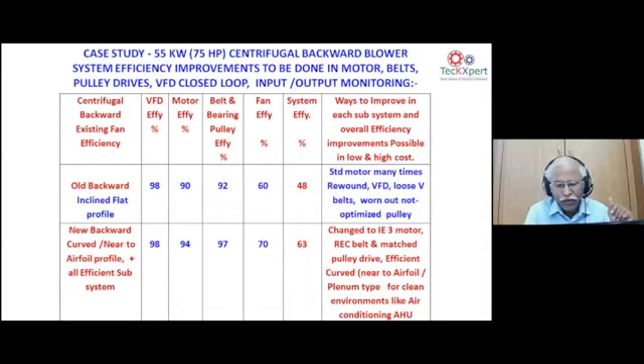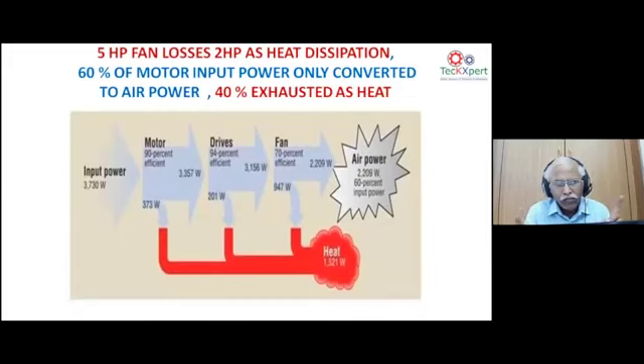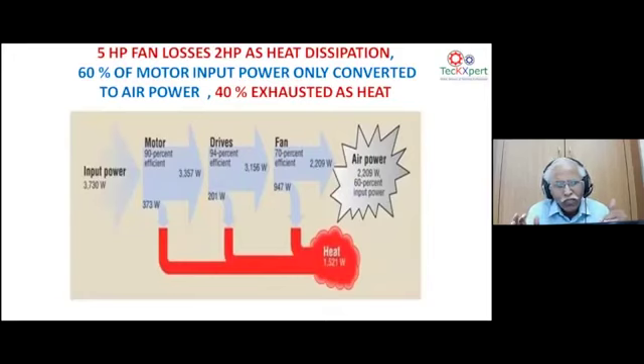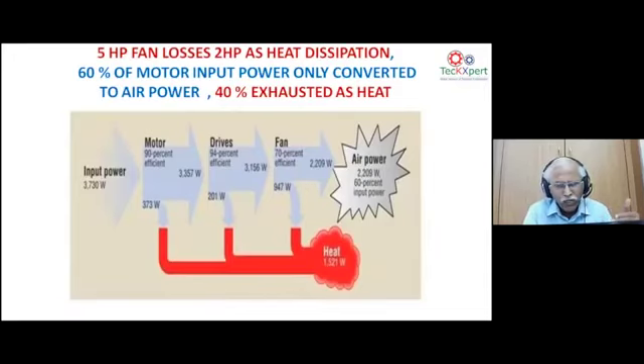This applies not just to the 55 kW machine. Even on a 5 HP blower, losses are significant: 60% of motor input power converts to air power, while 40% is dissipated as heat. With 3.7 kW input, motor output is ~3.3 kW, drive output ~3.2 kW, and after the fan at ~70% efficiency, only 2.2 kW of air output remains — a 1 kW loss in the fan itself, with 1.3 kW total heat loss.